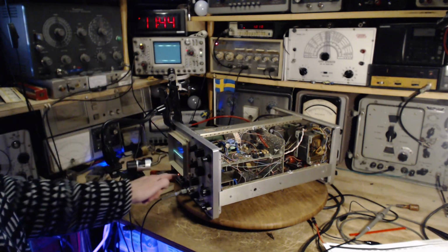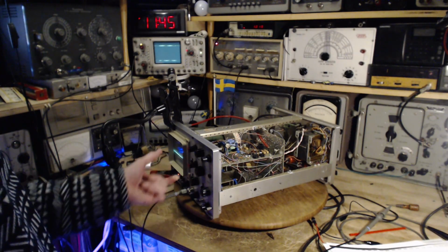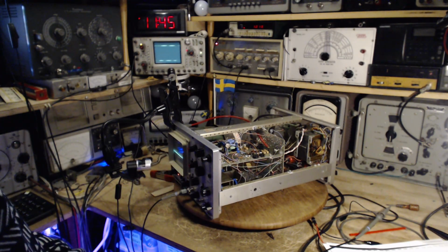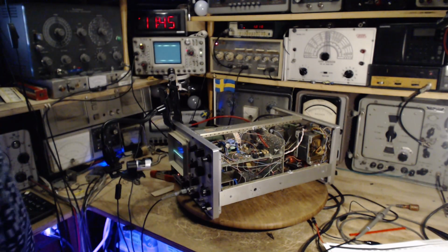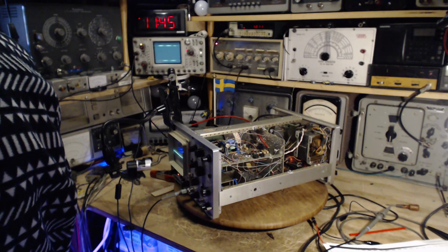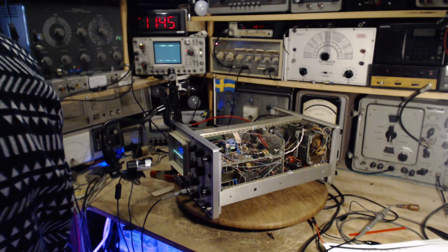Then switch to this calibrated, or let's say at this point uncalibrated output, and then calibrate to match. And in the worst case scenario, I've got 2 scopes that are both off, but off in the same way. Again, we're splitting hairs here. I think this is a real refinement, but let's see what happens.